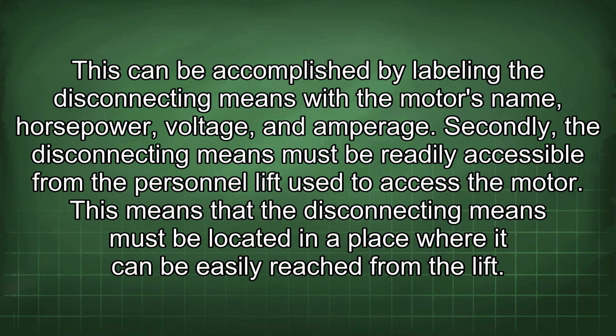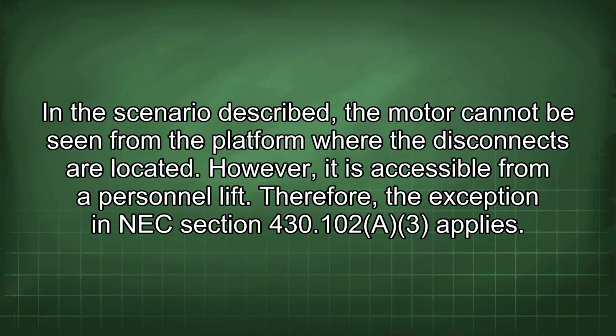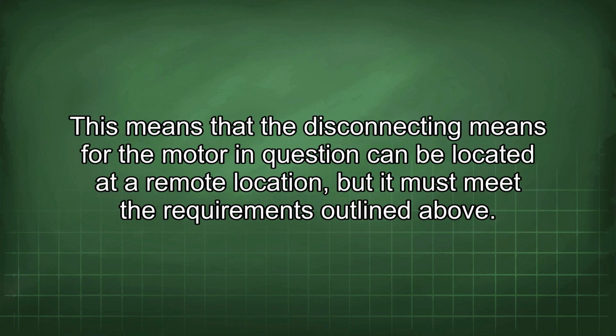This means that the disconnecting means must be located in a place where it can be easily reached from the lift. In the scenario described, the motor cannot be seen from the platform where the disconnects are located. However, it is accessible from a personnel lift. Therefore, the exception in NEC Section 430.102(A)(3) applies. This means that the disconnecting means for the motor in question can be located at a remote location, but it must meet the requirements outlined above.